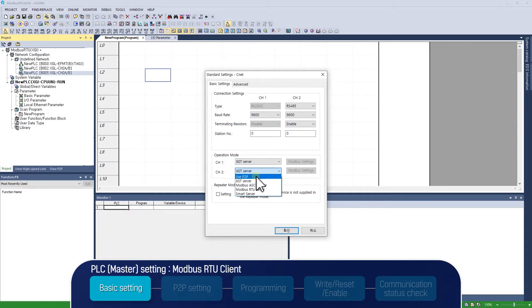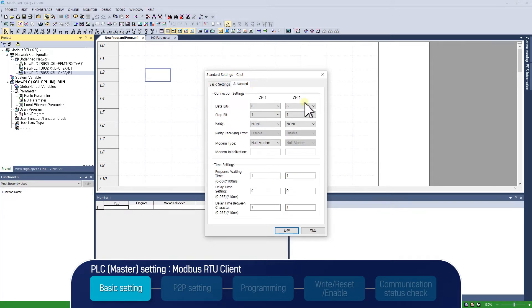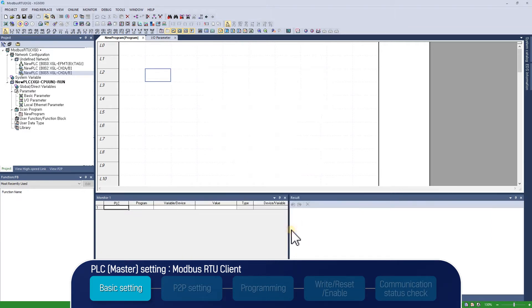Select use P2P of channel 2, as it works as Modbus RTU client. Choose 8 in data bits, 1 in stop bit, none in parity in connection settings of advanced. Then click OK to complete the standard settings of CNET module.